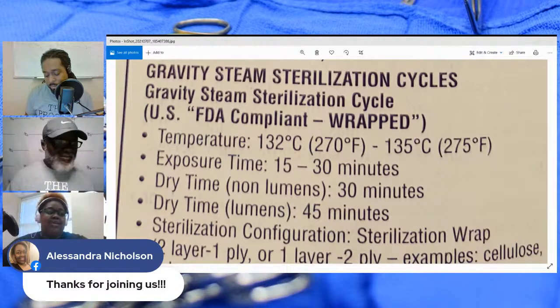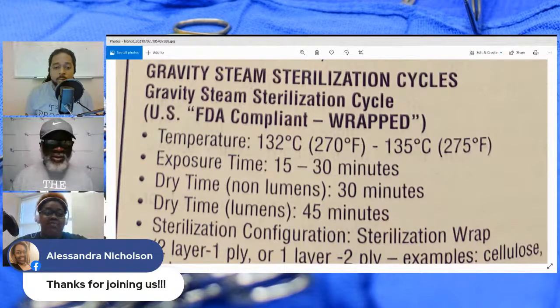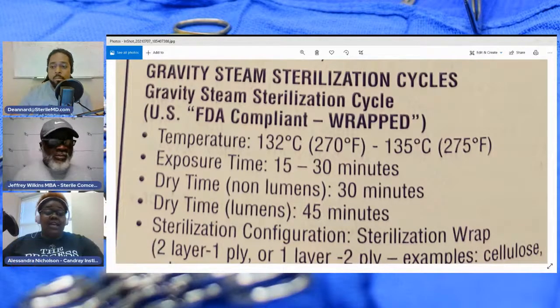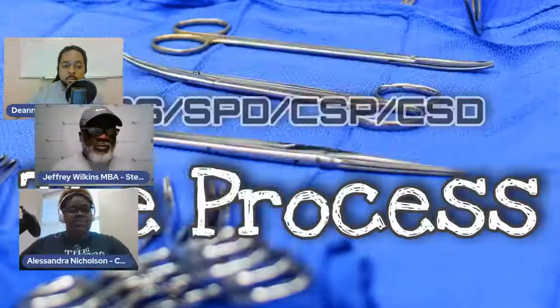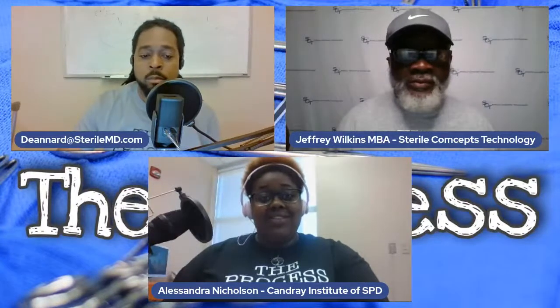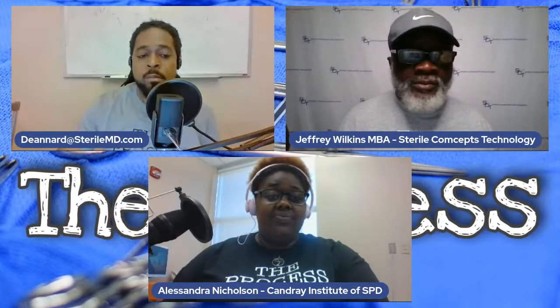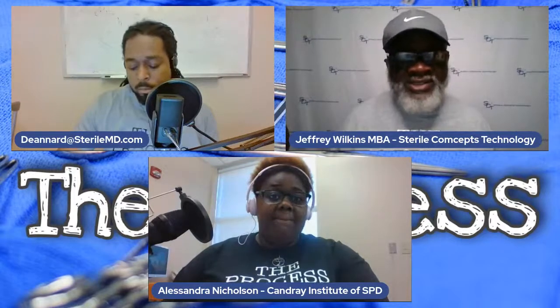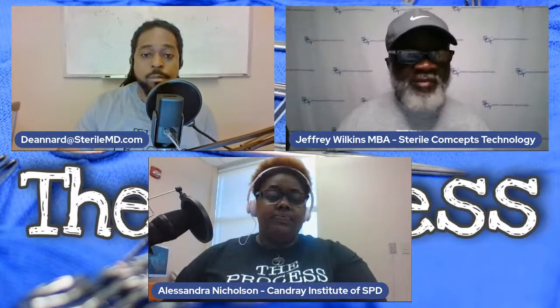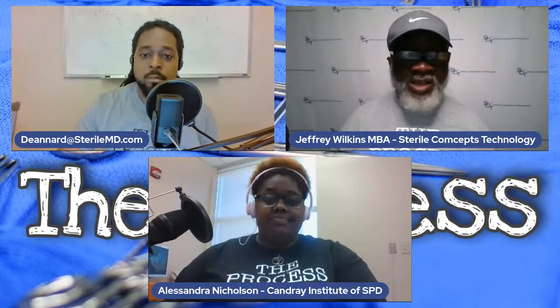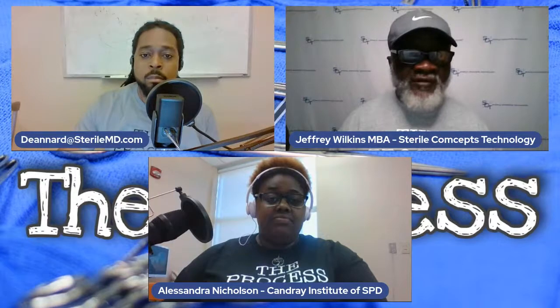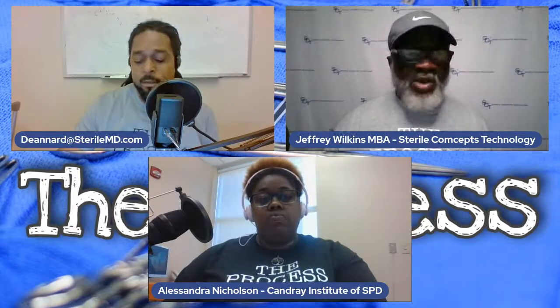But there are definitely times on the floor where your IFU does not give you all the information you need, and you still have that case that's going in a few minutes. So SPD techs and leaders get put into positions where you have to make your best educated guess as to what to do next, and that can be challenging because, like you said, when do you do that? When is it appropriate for you to make the best educated guess on what to do next versus calling somebody and getting some clarification on what I'm missing here in this IFU? Yeah, I mean, think about it. A lot of trays still have Pilling instruments in them, and then you have Codman Pilling, all these different instruments in it. You have to figure out which IFU is going to cover all those instruments, or get instrumentation that's all the same.